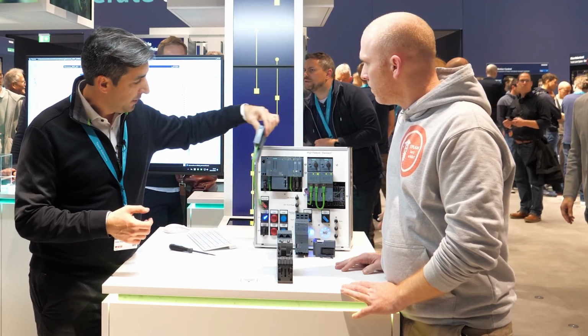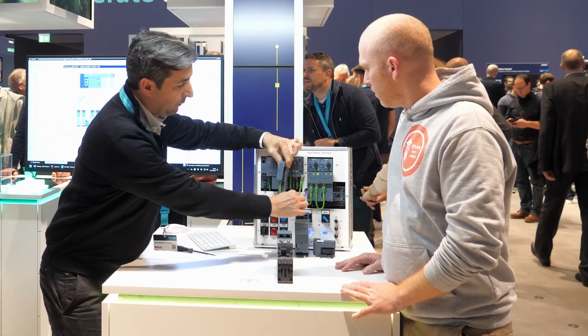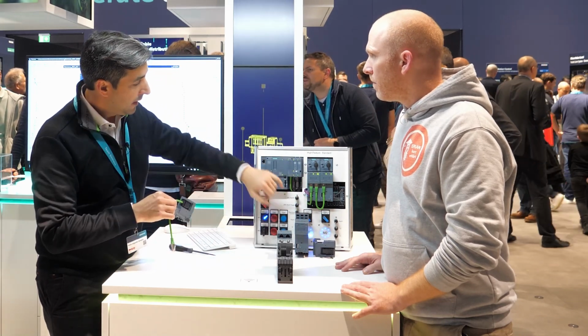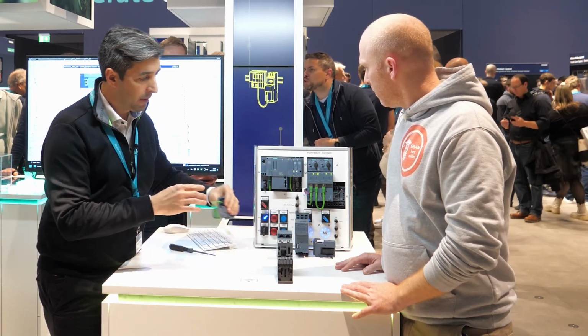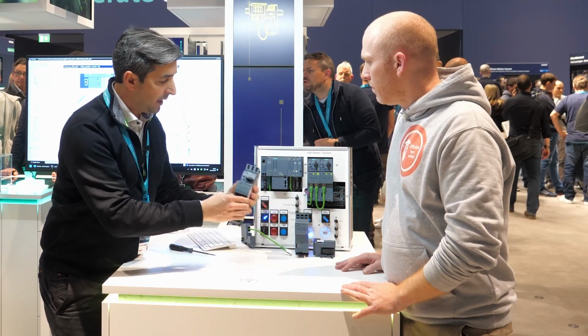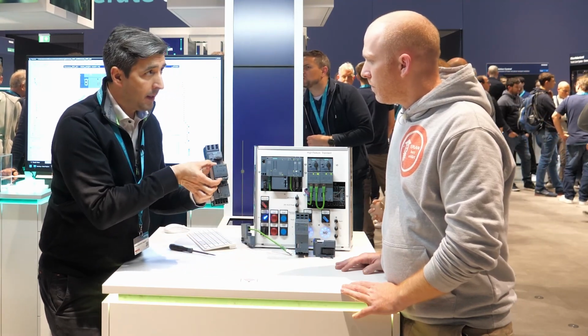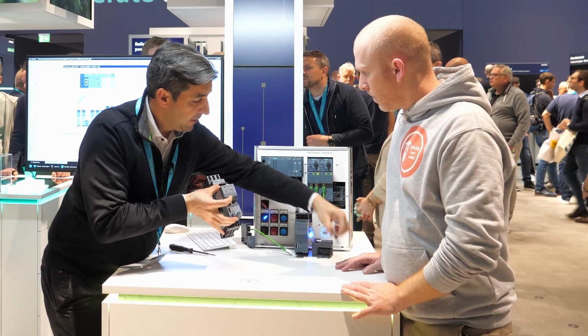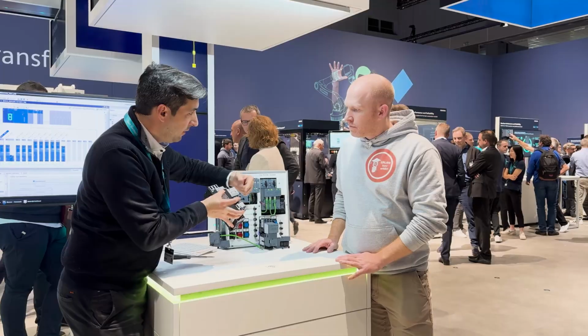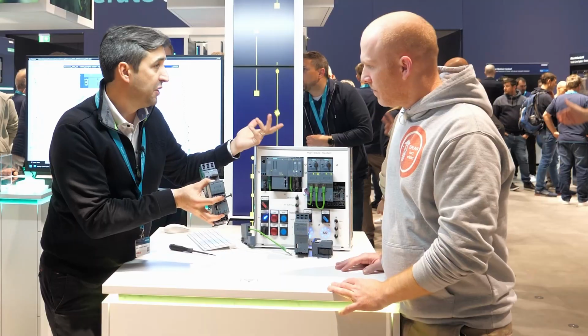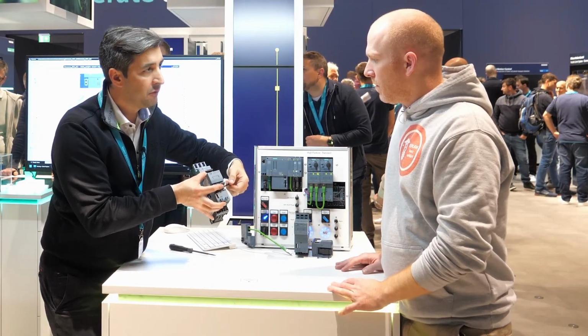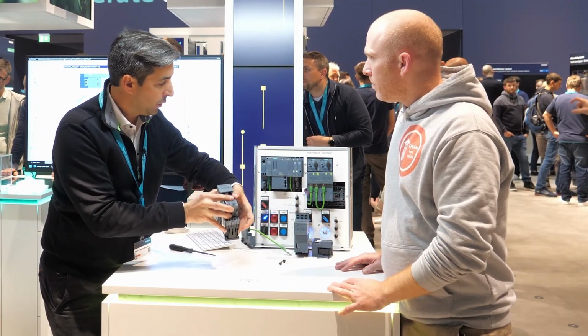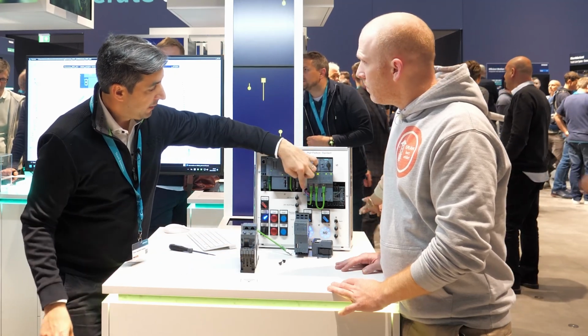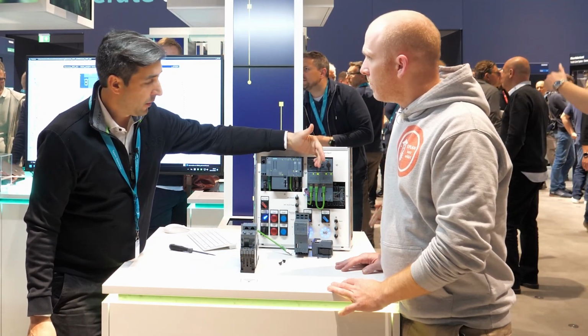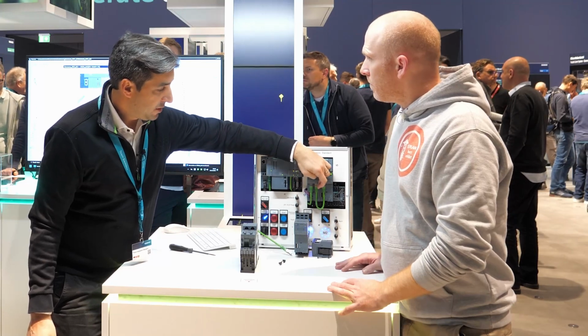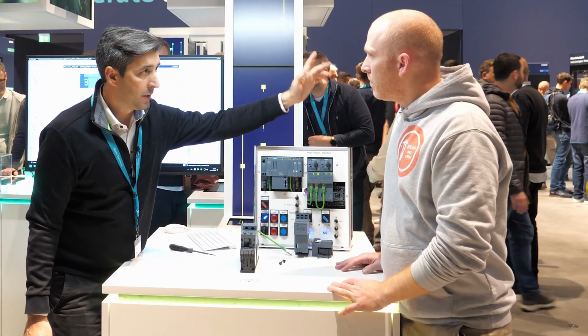So this module that you can see here also is an extension rack, and this goes from module to module up to 16 devices, and you have to provide the 24 volt power for the module. But also if you have side-by-side mounting, that is most of the cases by the cabinet, then you can have this small cable for the powering. And you can jumper the next one. Exactly, bridging the power for the next one to the next one up to 16 devices. In that way, the only wiring that you really have to do is just the wiring to the first device that brings the power for the rest, and then bring in just the connection cable with the green cable to the next one, to the next one, to the next one.